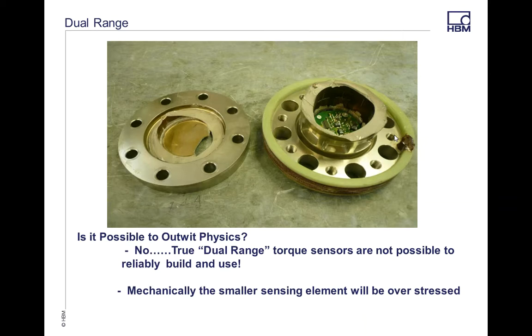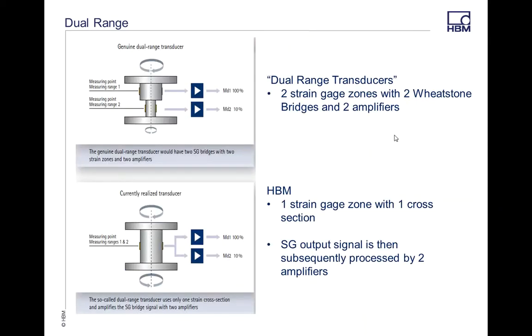You really can't outwit physics. So how do we do this? On the top, I've mentioned some transducers. They have a dual range with two strain gauges, two Wheatstone bridges, and two different amplifiers for two different diameters. Outside diameter and inside diameters, because they have to try to push the strain gauges through that. So that's going to be your weakest link, like I mentioned.